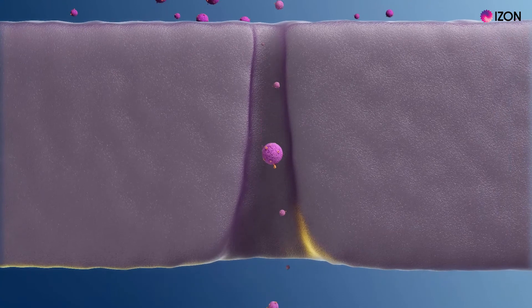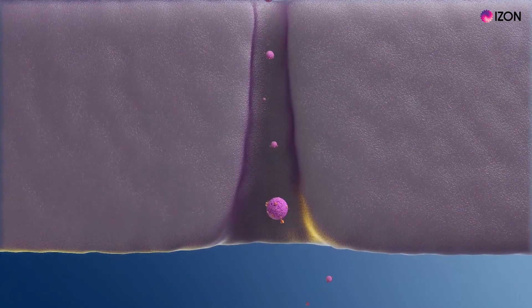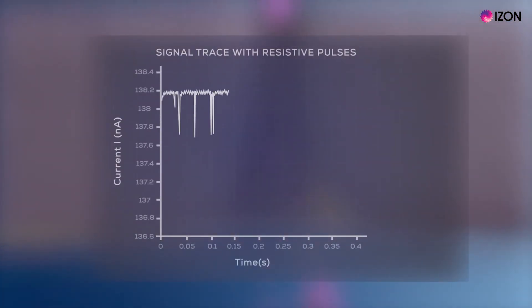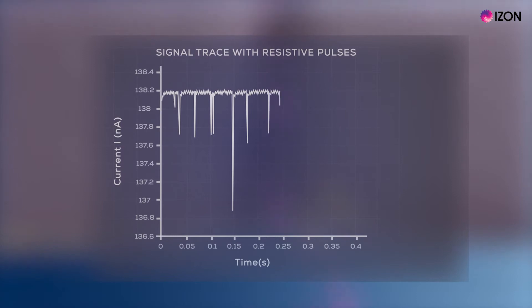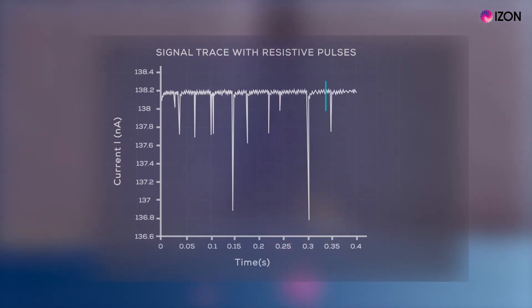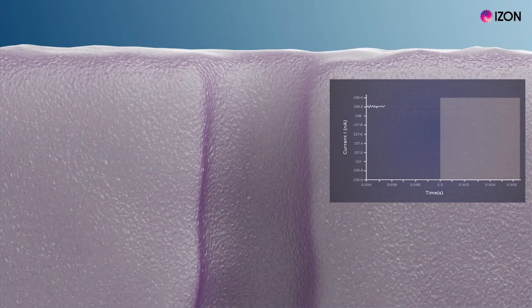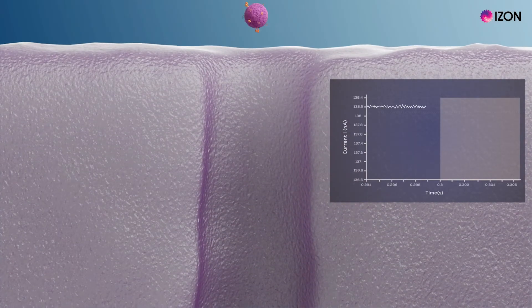The characteristics of this current blockade are used to determine particle concentration, particle size and particle charge or zeta potential, by measuring the number of pulses, pulse magnitudes and pulse durations, respectively.